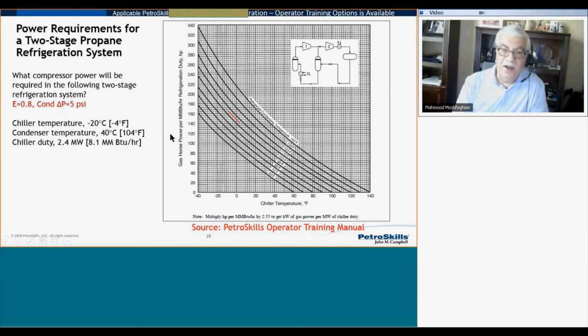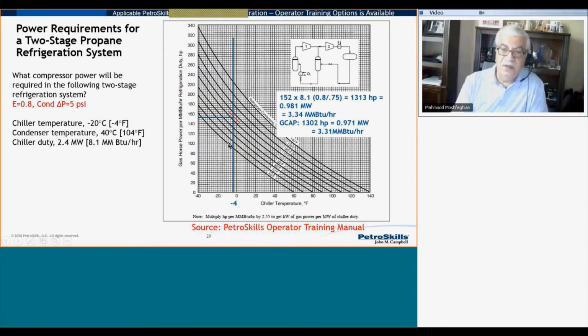If you don't have access to a computer program, you can use the operator training manual of the PetroSkills course. So all I need is the chiller temperature and condensing temperature. We did similar for the single stage simple refrigeration system. Again, I read the number here, 152 multiplied by 8.1 million BTU. This is the chiller duty, because this is million BTU per refrigeration duty, which is the chiller duty. Then I adjust for the efficiency. I get 1313, and GCAP got 1302.